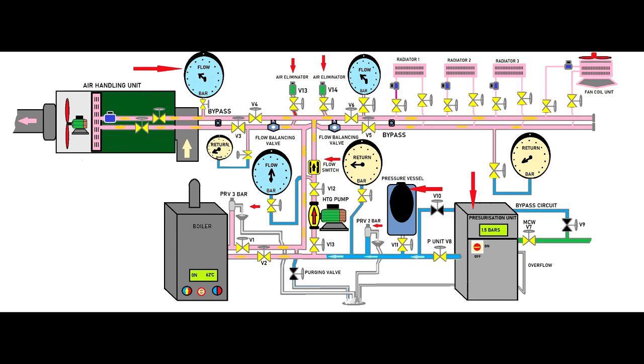So a good engineer is not looking only to the boilers or using a set of screwdrivers. You have an overview of the entire system. Watch the PRVs, watch the manometers if they're good - every single part of the system plays a very important role either on a system investigation or on the system functionality. A bad design can lead to trouble. Look at the pressure vessel, the rubber bellow inside. If it's too much abused it can be damaged inside. Once you lose that rubber bellow, you lose system elasticity.